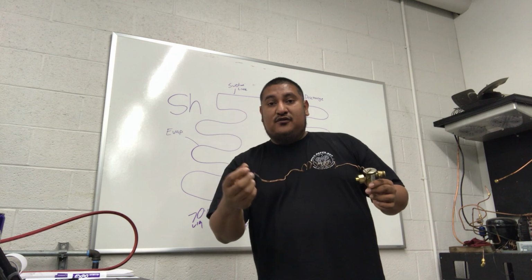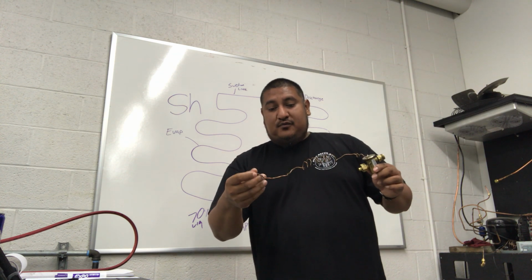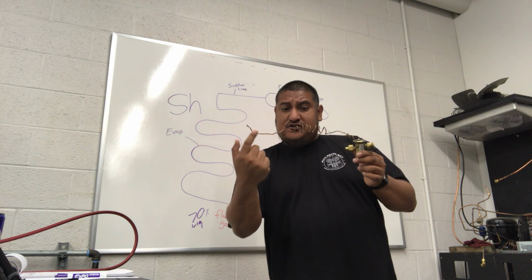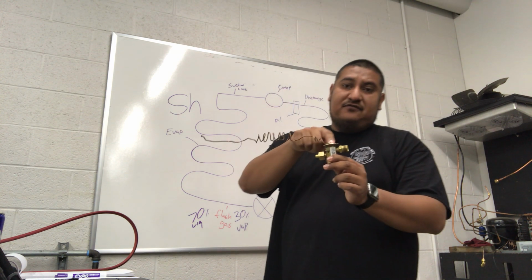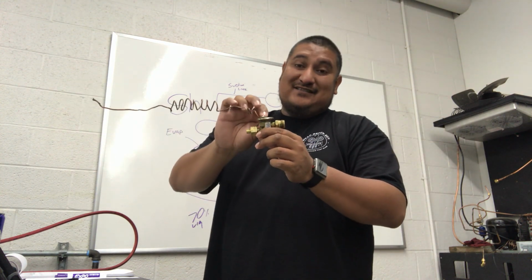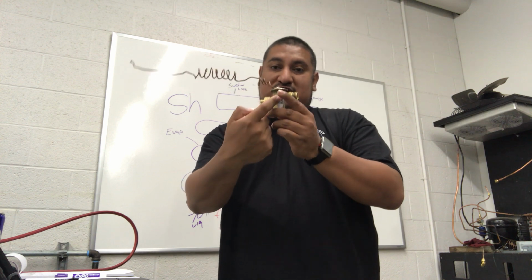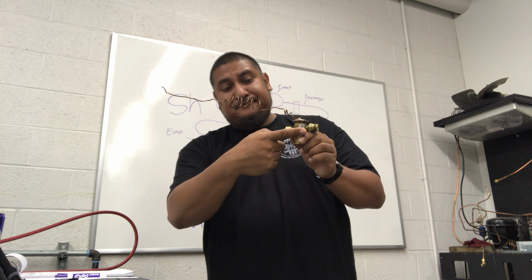When it starts to boil, it increases the pressure in here. The pressure shoots through this line to the top of my UFO, my diaphragm. As the pressure increases, it pushes down the diaphragm, which pushes down the valve down here and starts to open it up, which allows more liquid to come through.